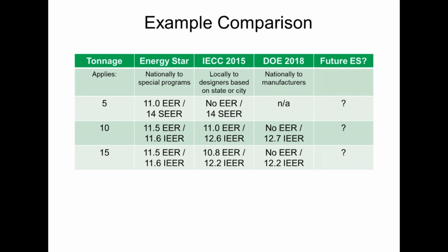Going forward, the new DOE rules will be very similar to the current code we have for IEER. And in a 15-ton example, same kind of thing: the local code is more stringent on the IEER, but less stringent on the EER. So you've got to look at each one individually.